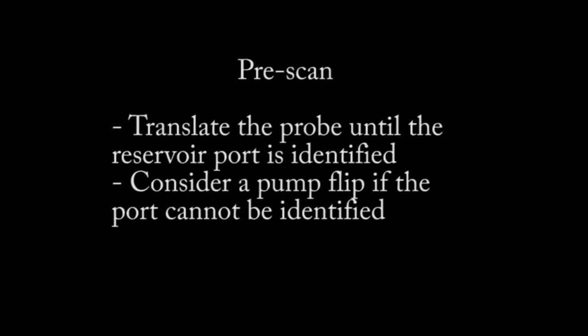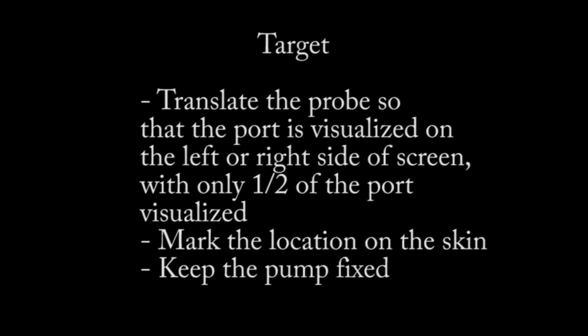Then with the pre-scan, once you know you're over the pump, you can translate the probe until you identify the reservoir port, and I'll show you this on ultrasound. If you scan or translate the probe from one side of the pump to the other and you can't identify the reservoir port, that might suggest that your baclofen pump has flipped 180 degrees. Once you've identified the reservoir port, this is my technique: I translate the probe so that the port is visualized on the left or right side of the screen with only half of the port visualized. Then I mark the location of the reservoir port on the skin by keeping my probe on the skin.